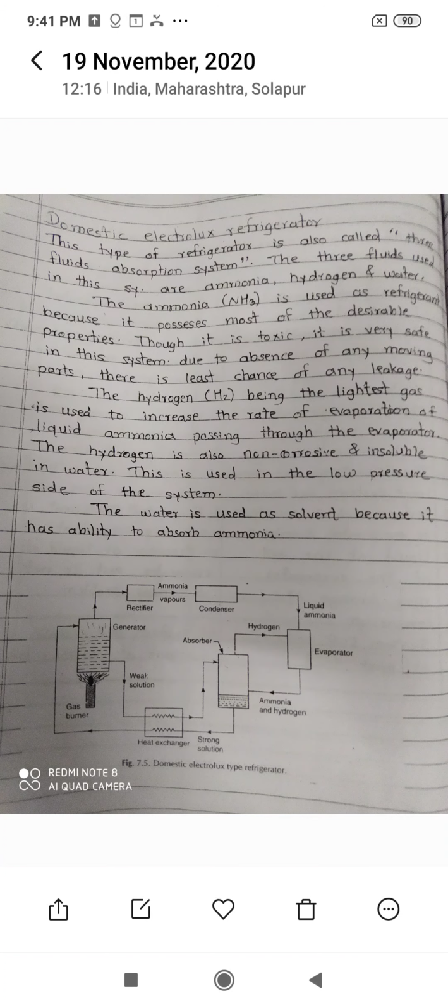So in the absorber, ammonia passes from the ammonia circuit to the water circuit. This strong solution from the absorber is passed into the generator, where it is heated and vapor given off rises to the separator.